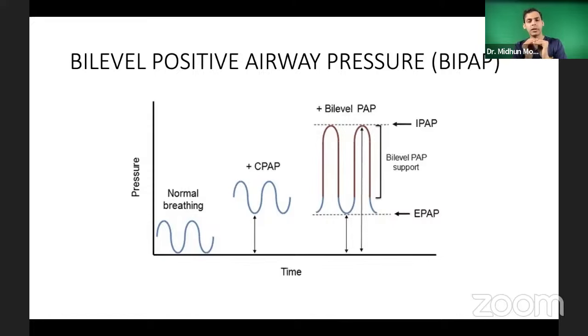During inspiration, you are going to give a higher pressure. So in the NIV machine, whenever you choose the BiPAP mode, the machine will ask you to set two pressures: one is called IPAP and the other is called EPAP. IPAP is inspiratory positive airway pressure, a higher pressure during inspiration. You are supposed to keep it more than the expiratory pressure. EPAP is the same as the CPAP, and it will help to improve your oxygenation by opening up the collapsed alveoli.